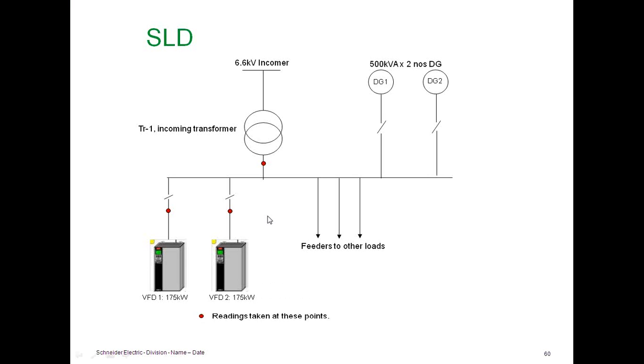This was the facility of the customer. They have a transformer. They use the transformer as the main power source, and if the transformer fails, they use a DG, 500 kVA, 2-number DG, to feed the power. So whenever they run the DG and switch on the VSD, there is 175 kilowatt 2-number VSDs, the DG trips with negative sequence relay. It is sensing harmonic negative sequence and is tripping. So the production loss for the customer was significant.